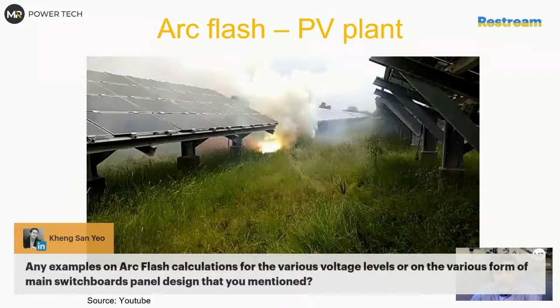So, what are the inputs required from the switchgear vendors to perform arc flash studies? Well, I assume that if you do a new project and you just have documentation, then typical data you will find on the nameplate. Usually you have a cut drawing where you can see the core orientation of the panel. You will have the short circuit rating of the panel, like 50 kiloamps, 1 second, which is important to evaluate the short circuit.